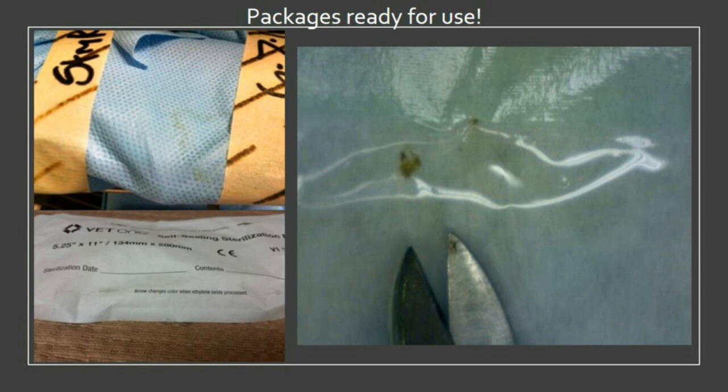So, packages ready to use, and here we are. We talked about it a little earlier on, that some of these water quality issues end up coming out in our packages, and we see them as where the water has dried up and left behind the minerals, the chemicals, whatever was in the water that we didn't want there. If I was in the operating room and I was scrubbing and opening these peel packs or about to open that wrapped item, and I were to see that, I would question it. I would question it absolutely.